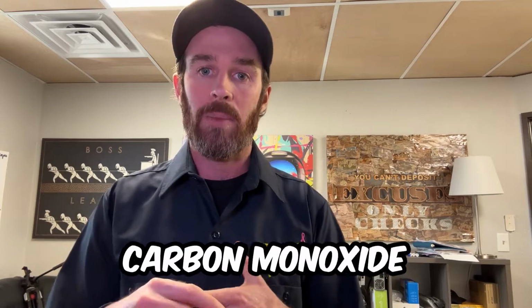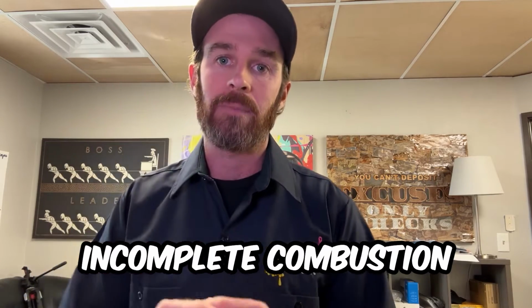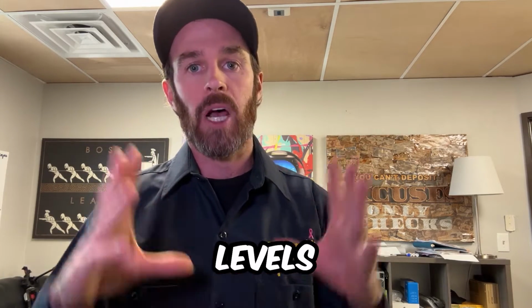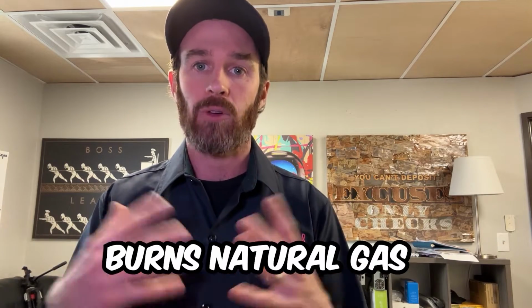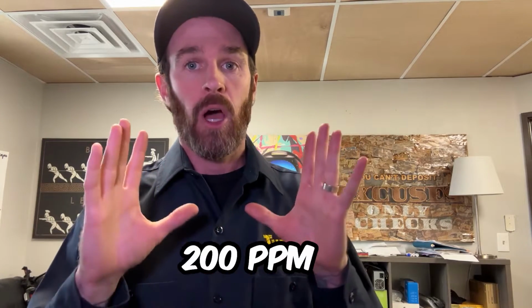And something to note about carbon monoxide is that your furnace, if it is tuned properly, should have relatively very low levels of carbon monoxide in the exhaust gases, and that is because carbon monoxide is a sign of incomplete combustion. Now, you will always have some levels of carbon monoxide in any sort of appliance that burns natural gas, for example, but if you have very high concentrations of it, like 200 ppm or more, then chances are your system is running rich or running lean, meaning that it has too much fuel or too much air in its mixture.